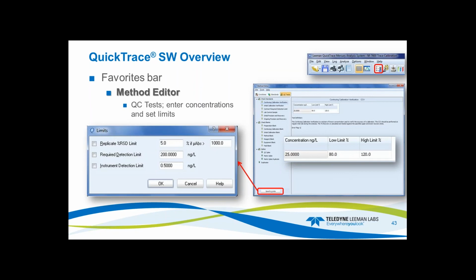Under QC tests, this is where you set up all the limits and the concentrations for your quality control. So you just click in it, and concentration value, if you're going to have a plus or minus limits, that's where you'd set that up. Also, under specify limits, this is where you can set up your replicate standard, relative standard deviation.